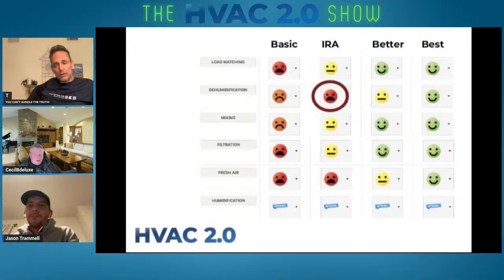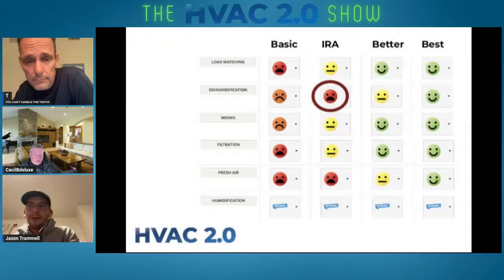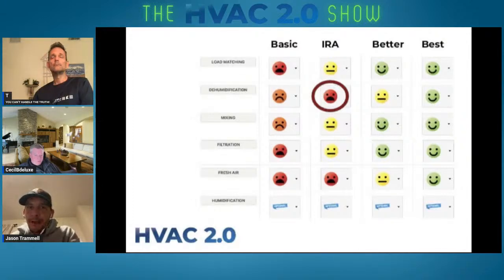Yep. Because I wonder if some of the different style coils work the same way as far as don't dehumidify as well, even if they're the same size or smaller size. I mean, all the manufacturers have the CAP coil. All the manufacturers have expanded performance for all their matches, and you can look at it and see the sensible to latent capacity and the ratio, the sensible heat ratio. And that's what Manual S is for, which is selecting equipment to meet the load calculation that you've done, so that it meets the criteria.